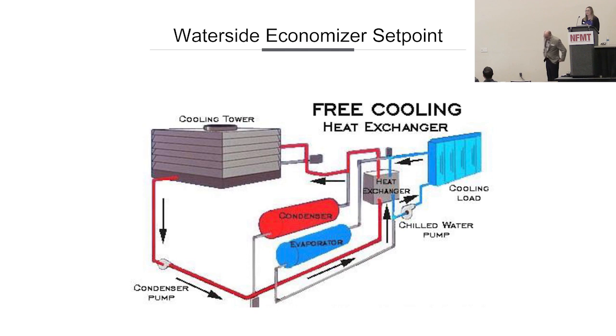So we noticed an issue with it being able to maintain those pretty strict set points, and we looked into it a little bit. Turns out the cold water basin heater in the cooling tower's set point was higher than the 36 degrees, so it was just a never-ending cycle of trying to cool off that heat that was gained through going through the cooling tower. So once we figured that out, changed set points, all of a sudden it's running way more efficiently.